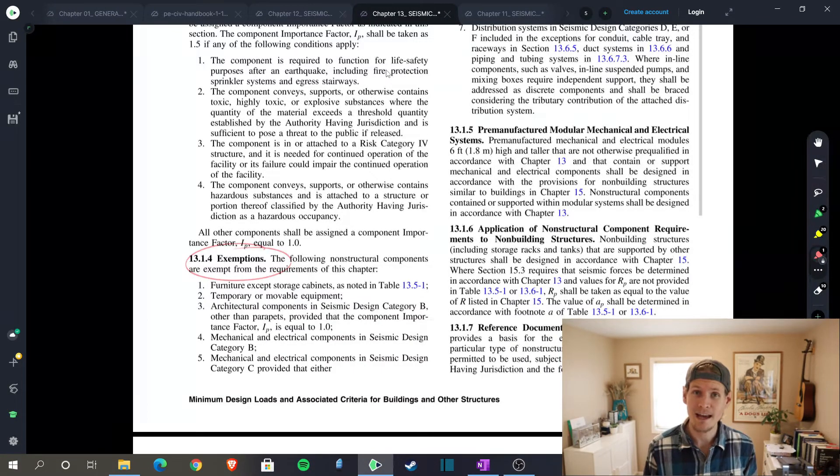exempt from having to actually do structural engineering for your anchorage of your unit. If you do fall into the exempt category, that means that you as an engineer don't need to actually calculate and design anchorage requirements for the units. So you always want to check these exemptions because if you're inside of them, then your job as the engineer is done.